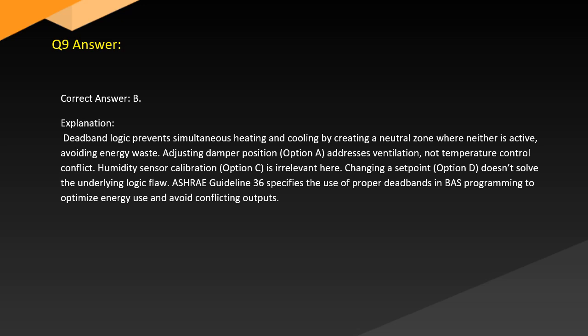Answer. Correct answer: B. Explanation. Deadband logic prevents simultaneous heating and cooling by creating a neutral zone where neither is active, avoiding energy waste. Adjusting damper position, option A, addresses ventilation, not temperature control. Humidity sensor calibration, option C, is irrelevant here. Changing a set point, option D, doesn't solve the underlying logic flaw. Guideline 36 specifies the use of proper deadbands in BAS programming to optimize energy use and avoid conflicting outputs.